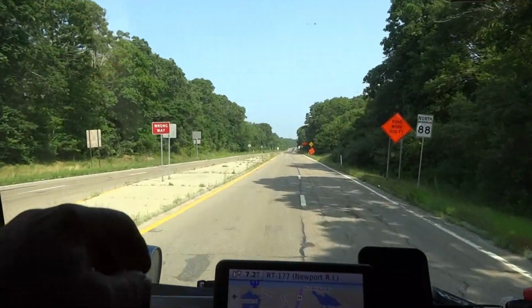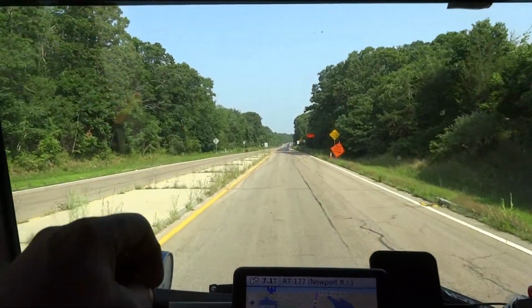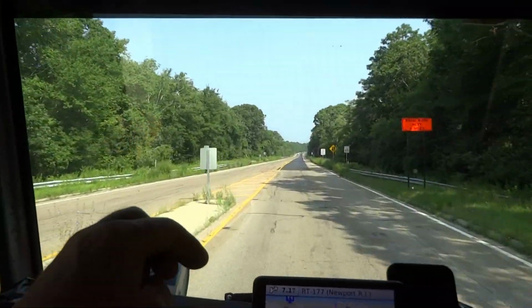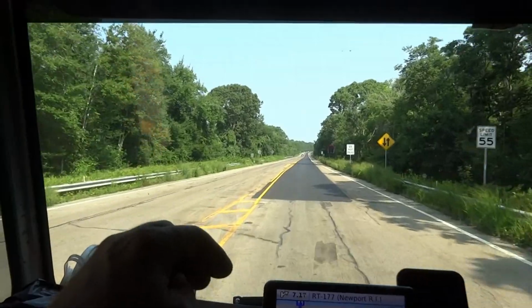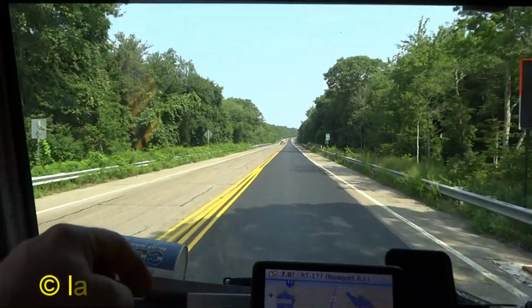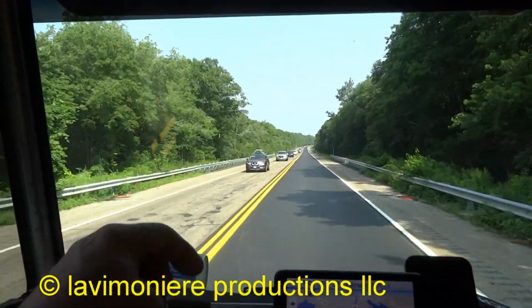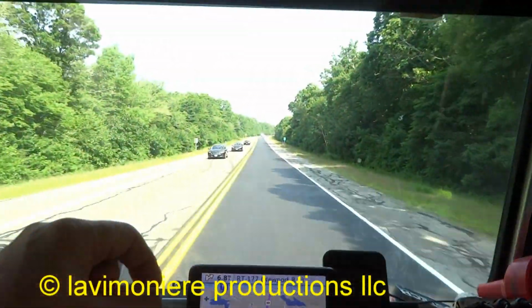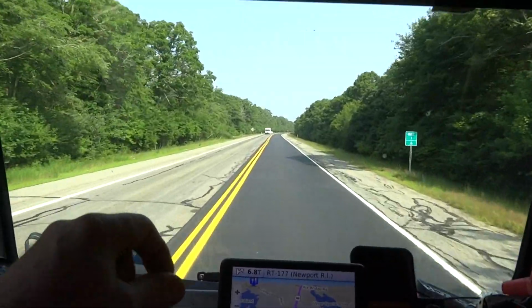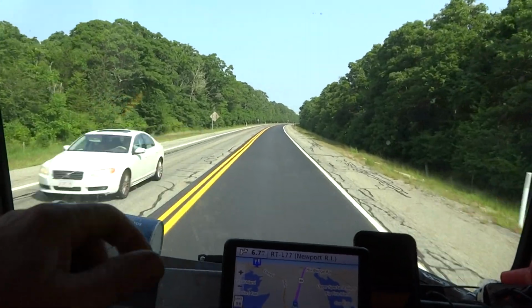All right guys, I got the model and serial number off that air handler. I'm gonna call in and see what the availability is of that TXV, and he wants a price, so I'll give him a price on changing that out, and give him a call back, see if he wants to do it. Stuff like that, I like to do T&M. He wants a price, it's gonna be a high price. I gotta pull that coil out of it to get to that TXV. I mean, you have to unbraze it, and braze a new one in there. Next level, mama, next level.